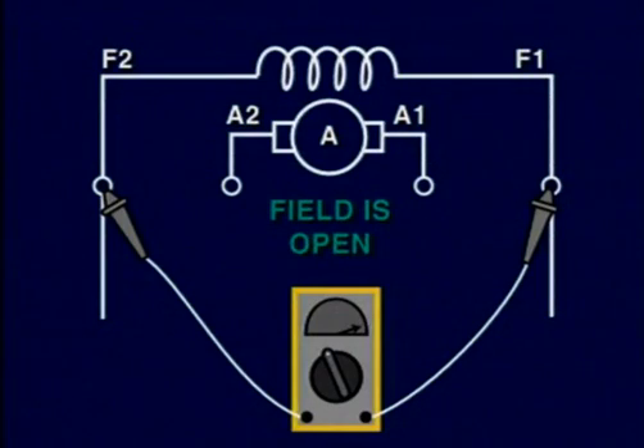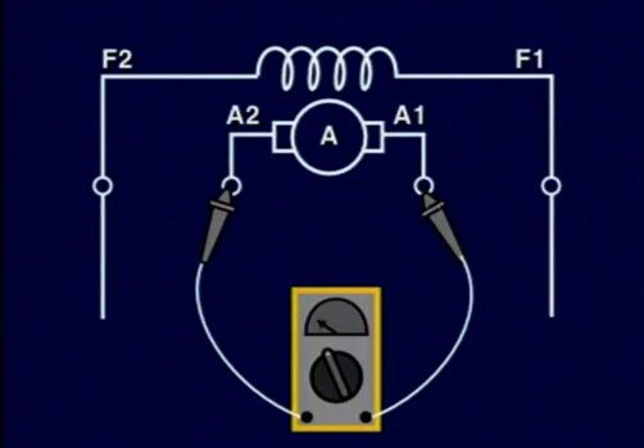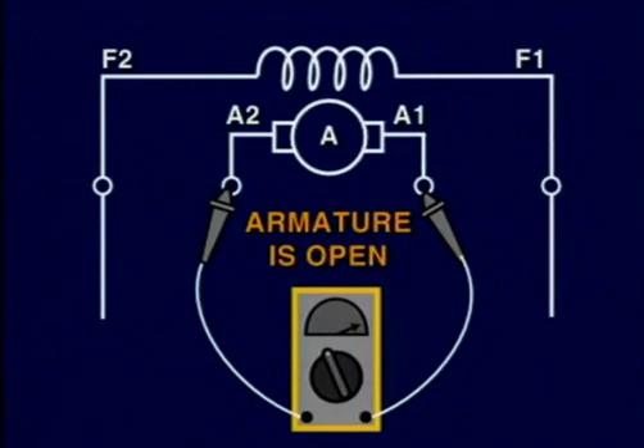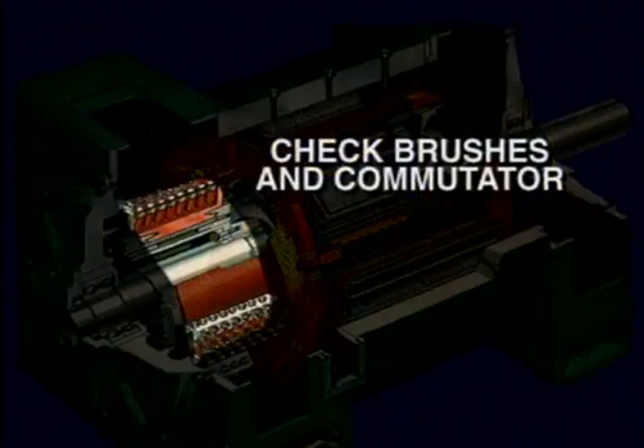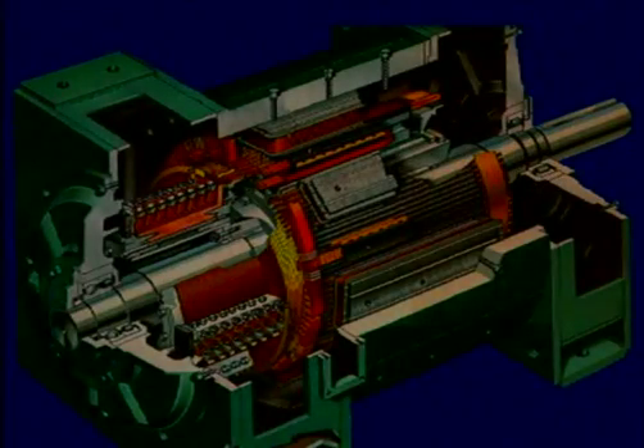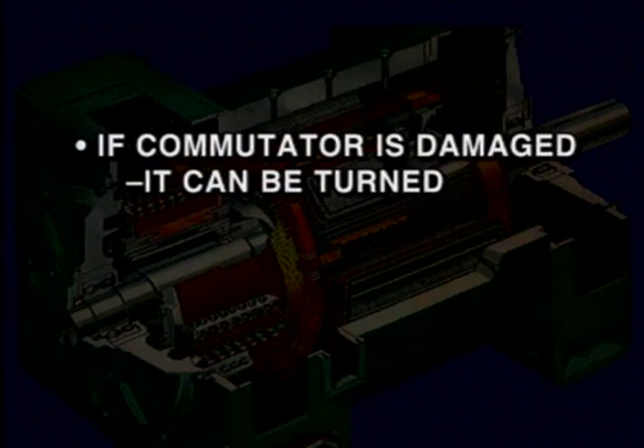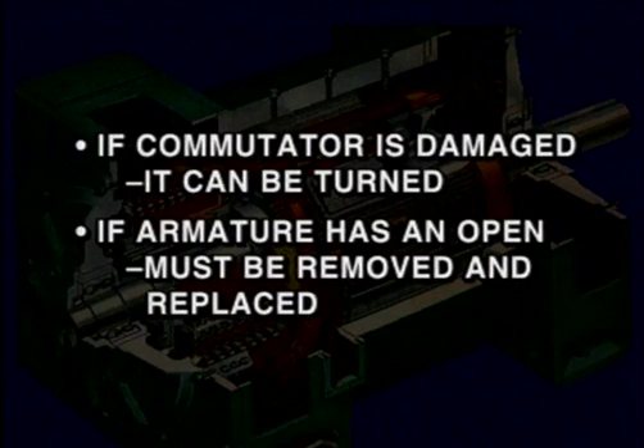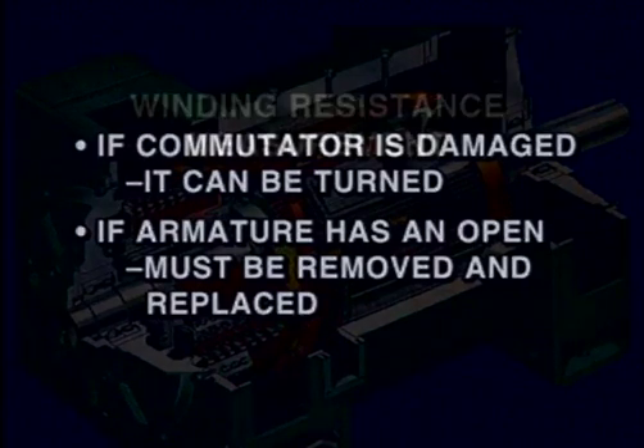The armature should be tested next by placing the ohm meter across the A1 and A2 terminals. If there is a resistance reading, the armature is okay. If it shows an infinite resistance, the armature has an opening in its winding. Make sure you also check the brushes and commutator to check for damage and see if the brushes are worn out or not properly seated. If the commutator is damaged, you can have it turned down in a lathe by a machinist. If the armature has an open, you must remove and replace the motor. In some cases, you may be able to replace only the armature without removing the whole motor.